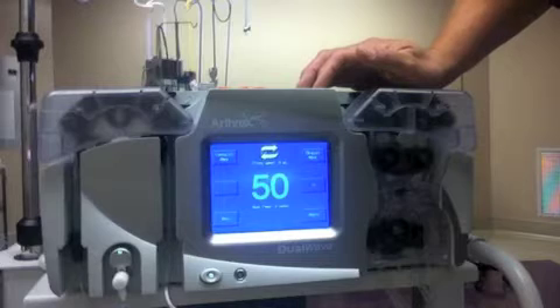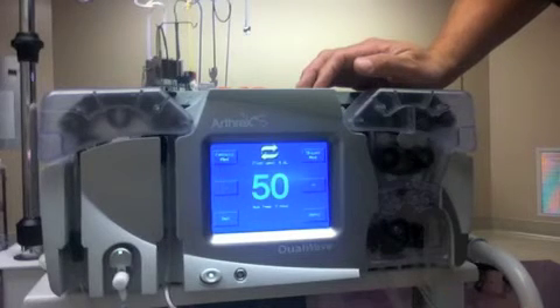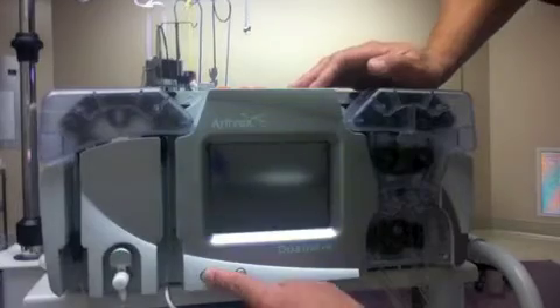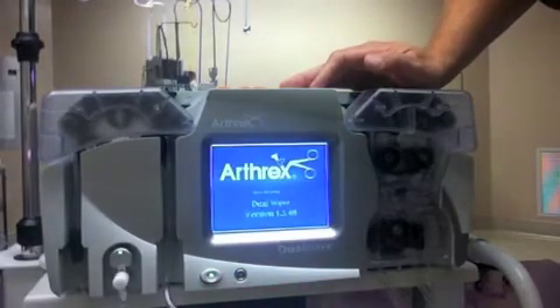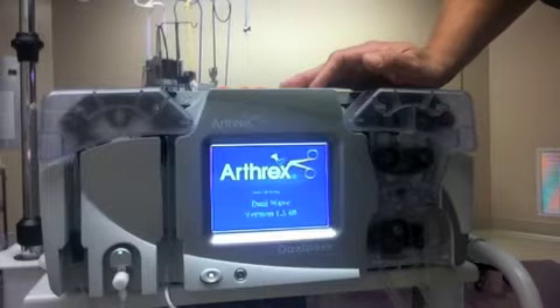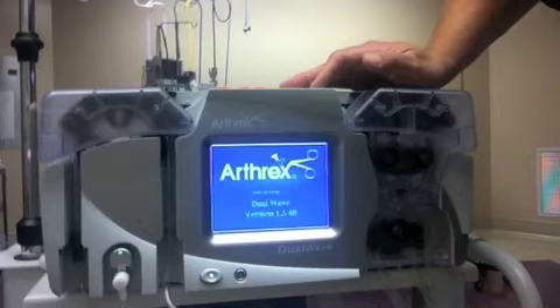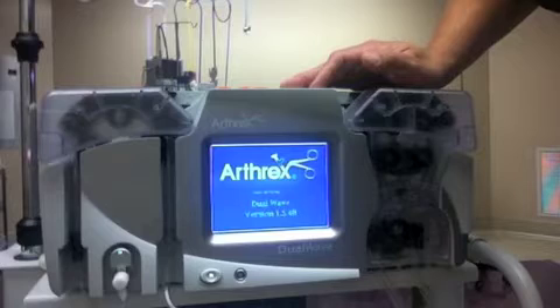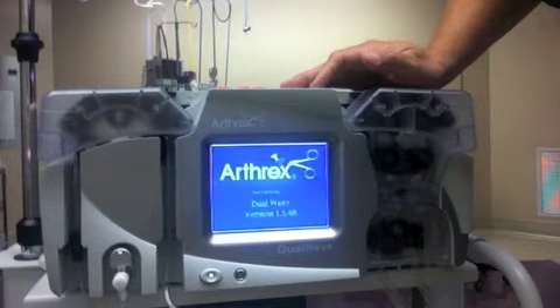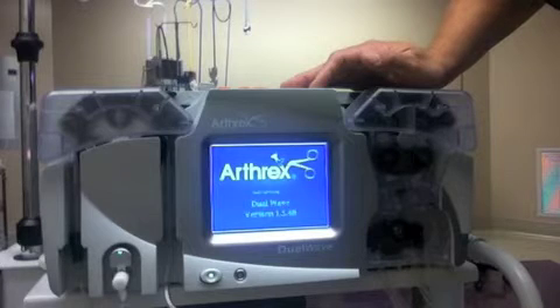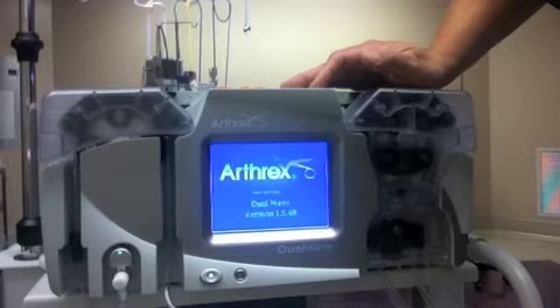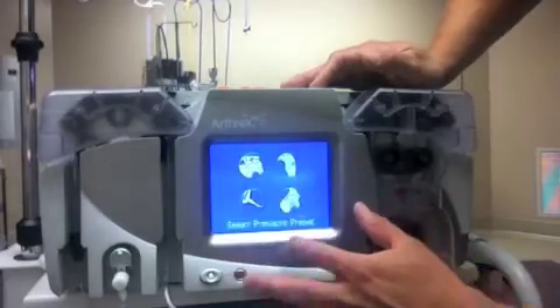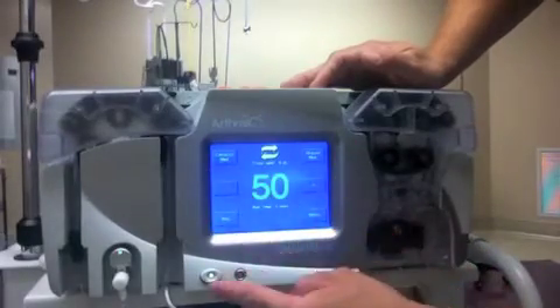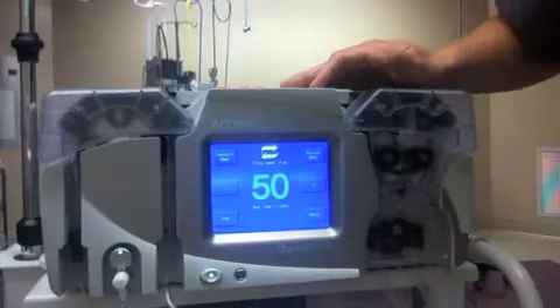So the best method, I believe, is to connect everything and then simply just turn the pump off and back on, allow it to go through its initialization period, select the proper joint, and then you're good to go. As far as priming of the pump, you simply hit run and allow for all the bubbles to go out of the line onto the sterile field, and once all bubbles are out, you're good to go. At this point, having been spiked, you just hit run and that's it.